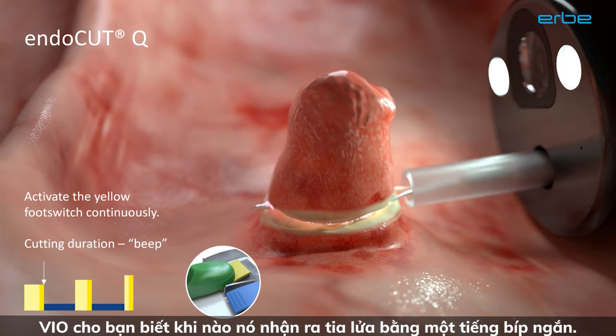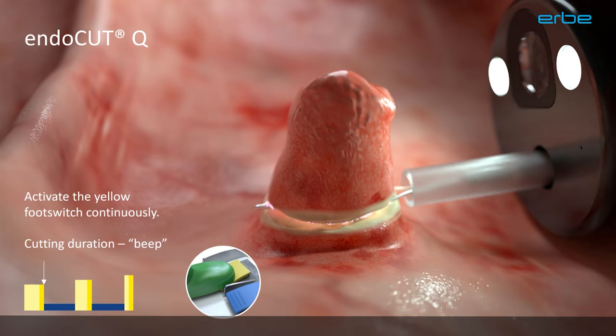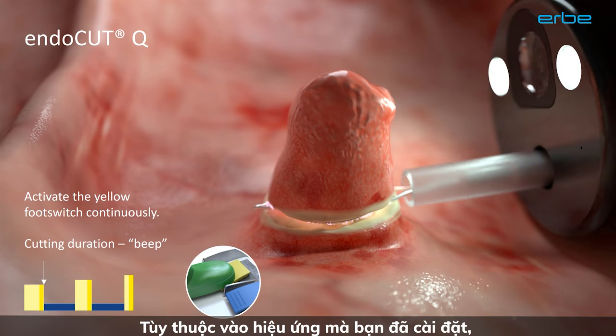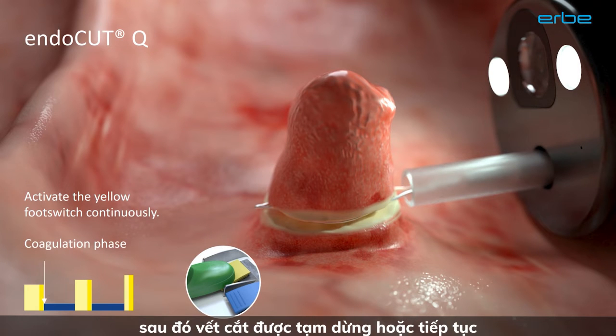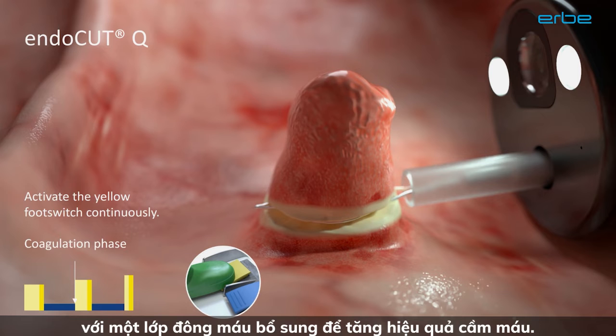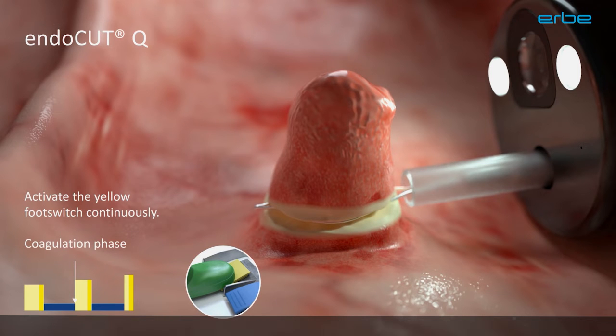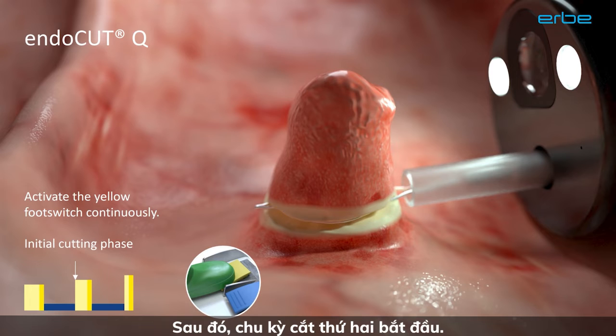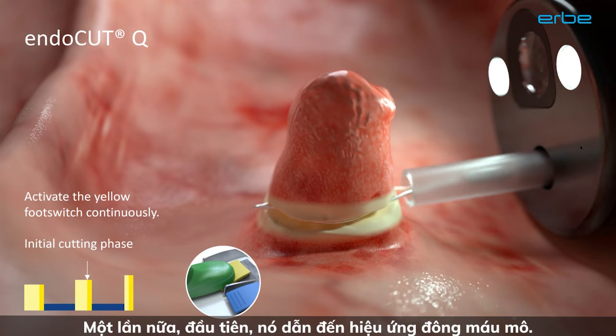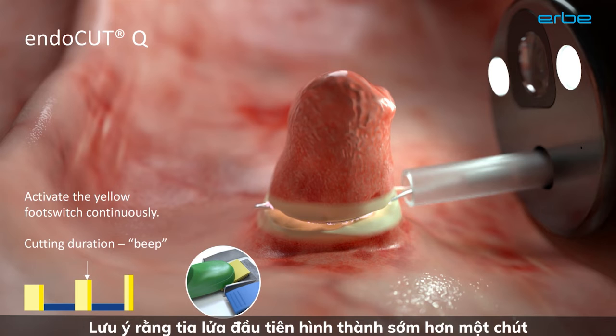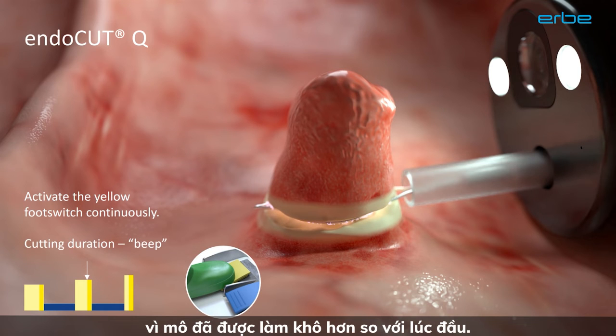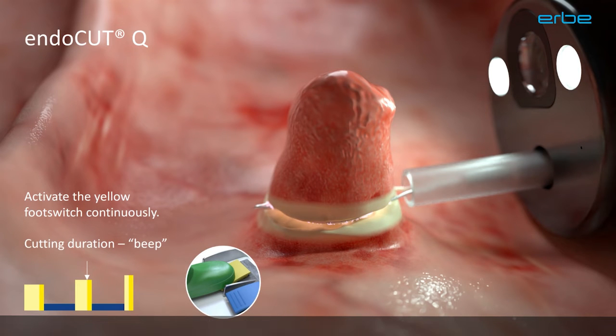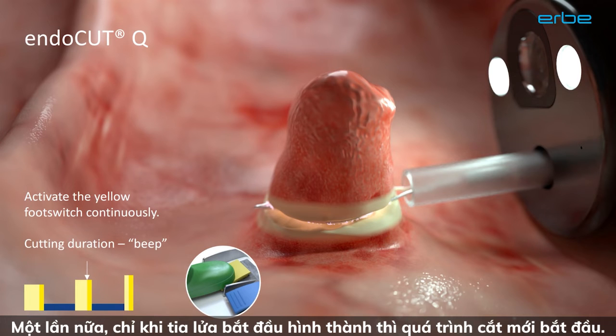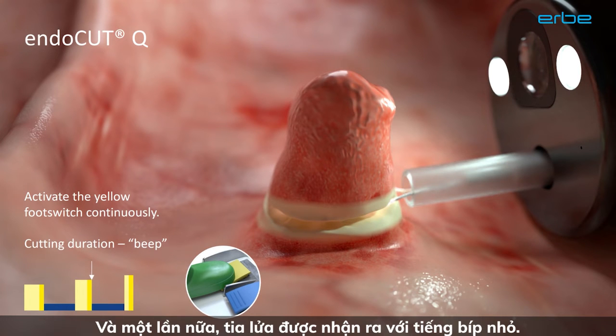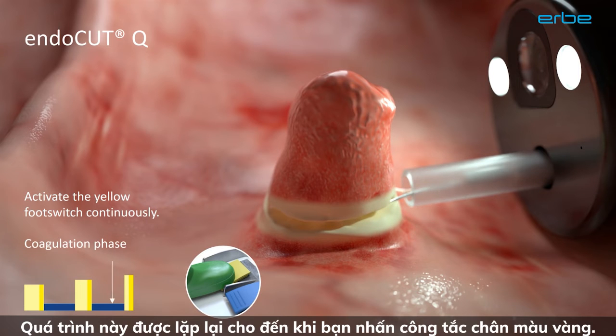Vio lets you know when it recognizes the sparks with a short beep sound. Depending on the effect setting that you have selected, EndoCut then either makes a pause or continues with an additional coagulation to increase the hemostatic effect. Then the second cutting cycle begins. Again, first resulting in a coagulating tissue effect. Note that the first sparks form a little sooner now, because the tissue is already more desiccated than in the beginning. Again, only when the sparks start to form, the cutting begins. And again, indicated by a little beep. This process is repeated as long as you press the yellow foot switch.